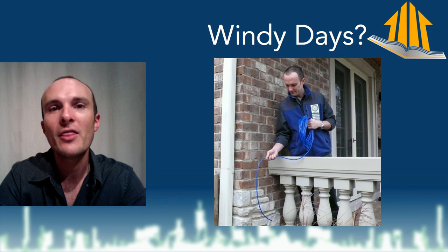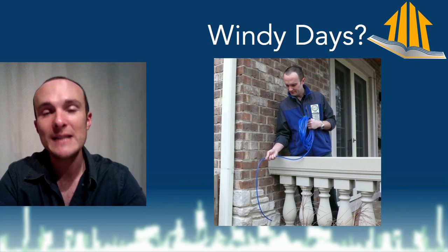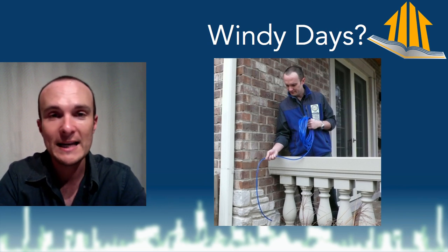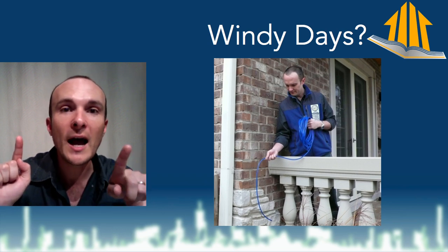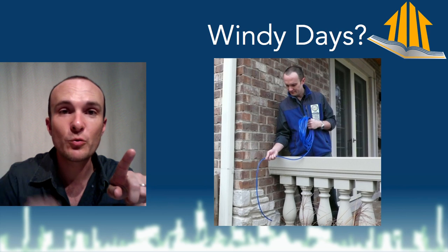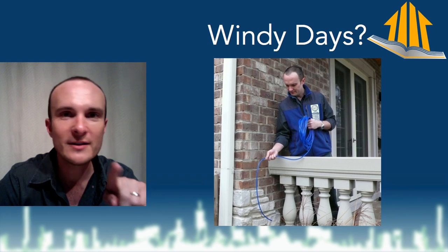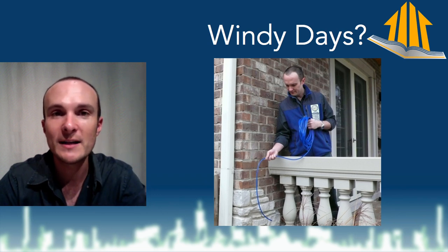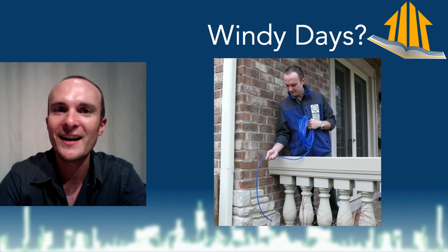But there's something else: the location of the hose. The hose that I'm dropping in this picture is called the reference hose. That's the hose that is going to serve as the anchor. Whenever you take a pressure measurement in home performance, you're taking it in a certain location with reference to another location. So the reference has to stay put — it is your anchor. If the reference starts moving around, that's no good, because the anchor you're depending on is moving. In order to fix this, you might choose one of several ways that are commonly used.